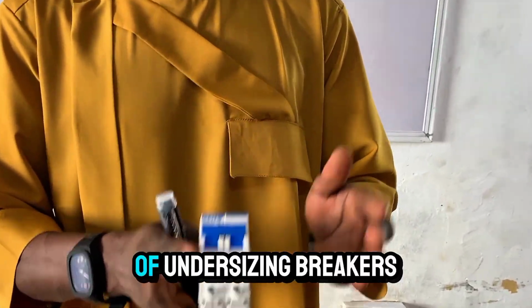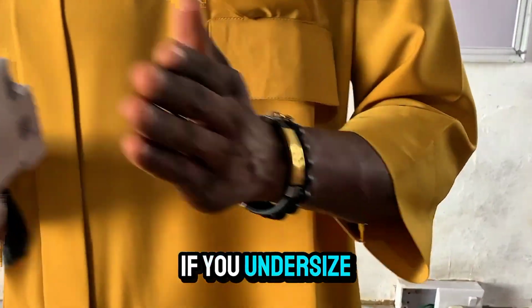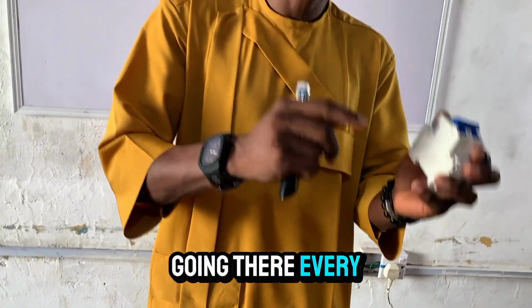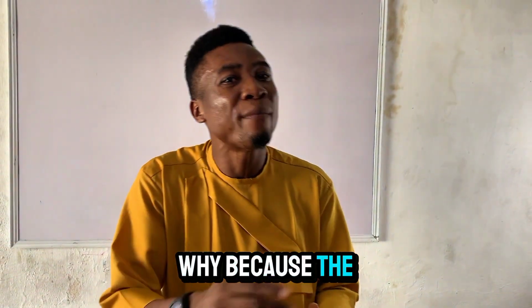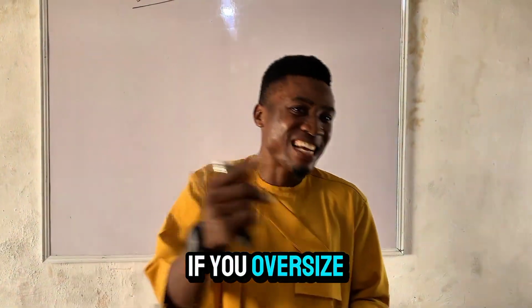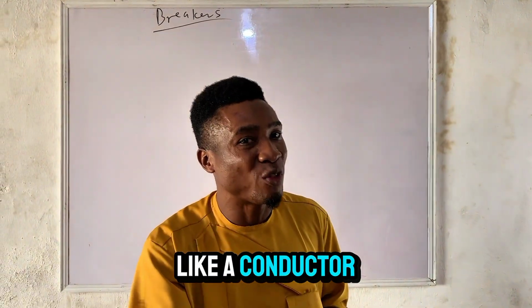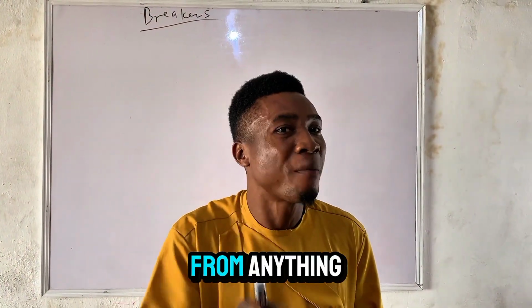One of the issues technicians face is undersizing breakers. If you undersize a breaker, you will be going there every day to re-energize it, because the breaker will keep tripping. If you oversize a breaker, it means the breaker will be working like a conductor - it's not going to protect your load from anything.